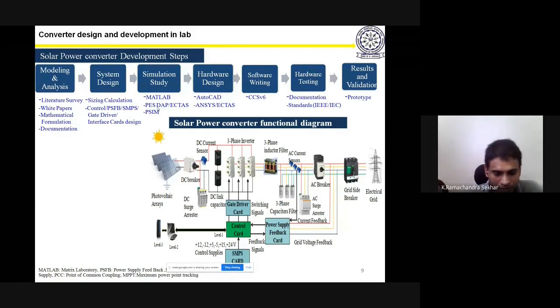See, what happens here: intuitively, first we set the modulation index of the inverter to exactly match the grid voltage. It's like a dam - when you open it, you don't want water to flow from one side to the other, so you maintain both sides at the same potential, the same energy level. Similarly, we adjust the modulation index such that the inverter voltage is exactly equal to the grid voltage initially. That means when we integrate, no current will flow, meaning no power is flowing.